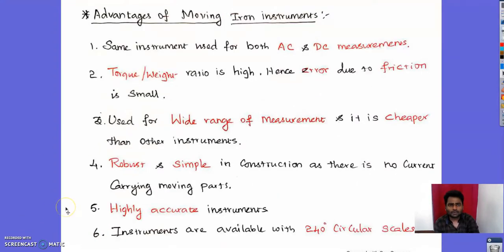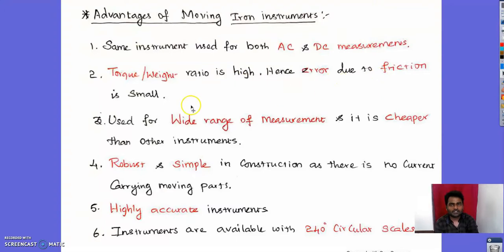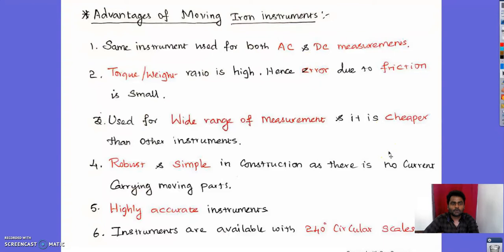The advantages of moving iron instruments are: the same instrument can be used for both AC and DC measurement; the torque-to-weight ratio is high, so friction error is very small; it is suitable for a wide range of measurements; it is cheaper than other instruments; the construction is simple and robust since no current flows in the moving part; it is highly accurate; and instruments are available with 240-degree circular scales.